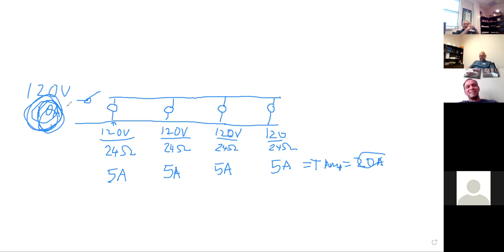So here's the thing. If a generator is only providing 10 amps, can a generator provide more amps? Sure, it can. Otherwise, I can't power anything with it. But yet the demand is higher than what the generator can put out. Correct. That's overload. What happens to the generator? It trips the breaker. It trips, right.